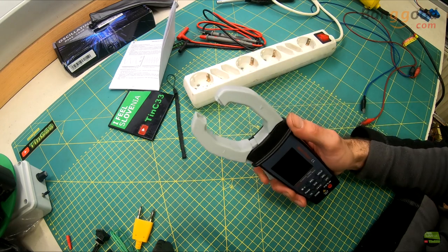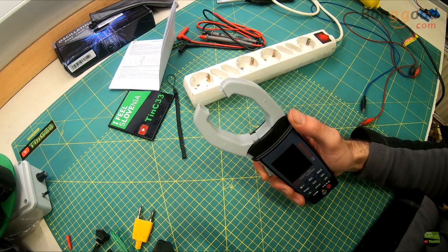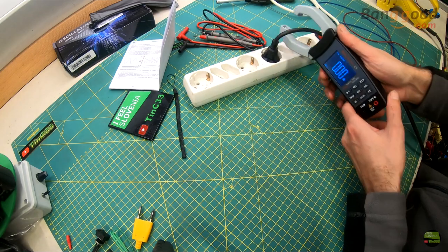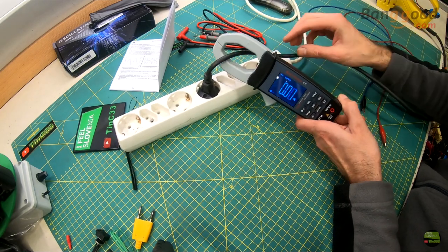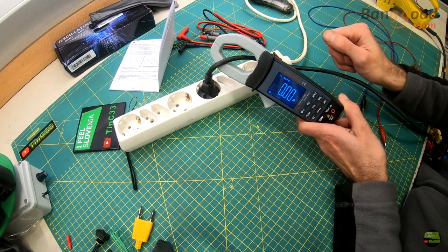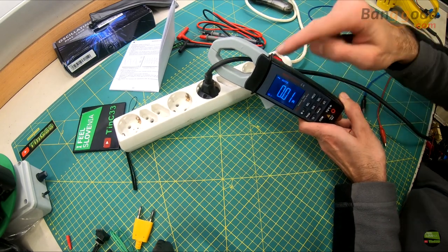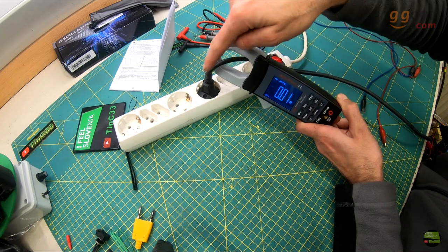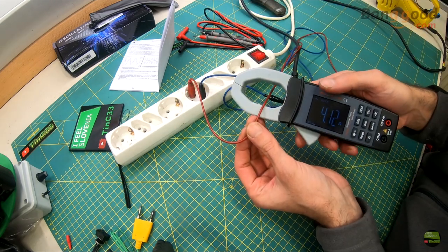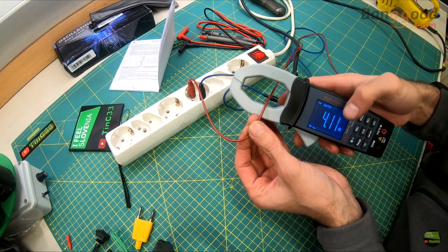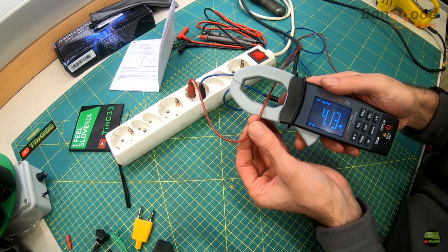The best function of that meter is the clamp for contactless current measurement. You know that we can't measure current on the cable because incoming and outgoing current are the same and show as zero. That's why we need to measure on separate wires.